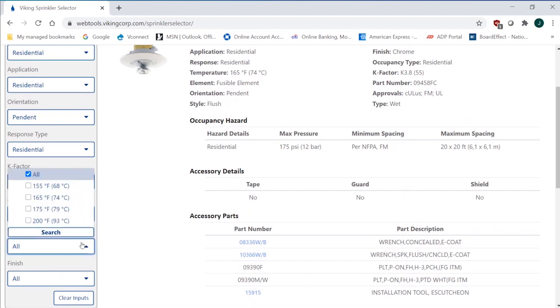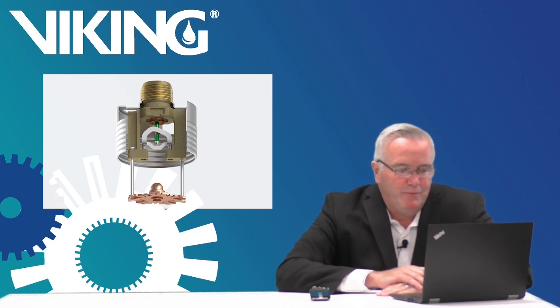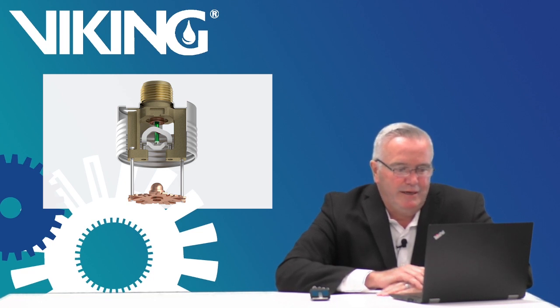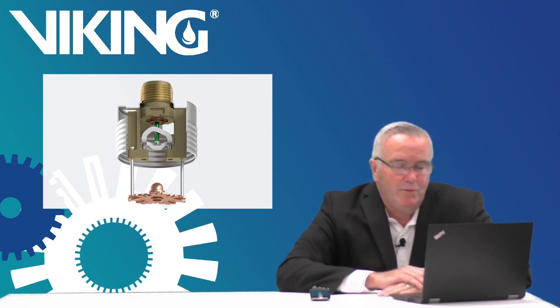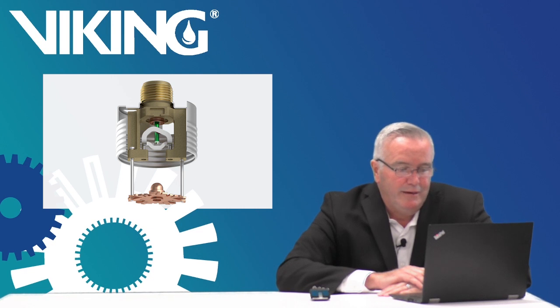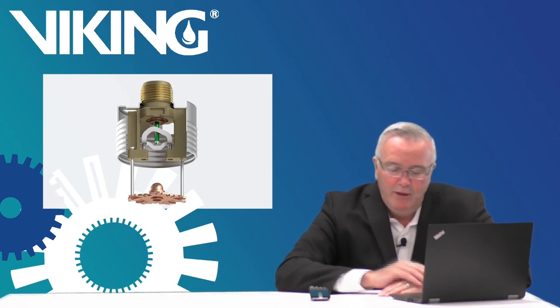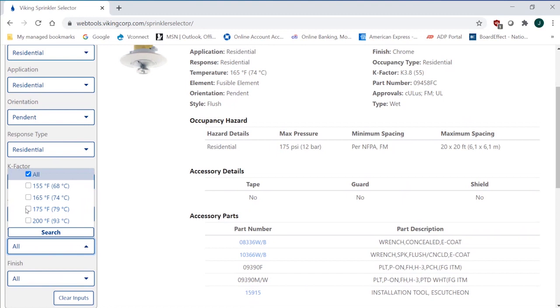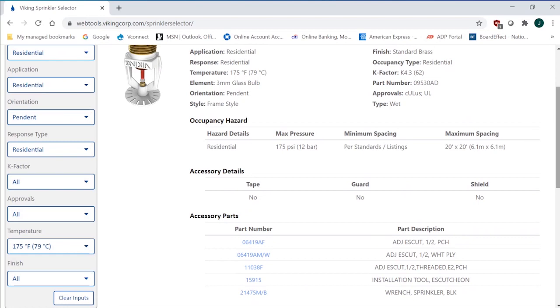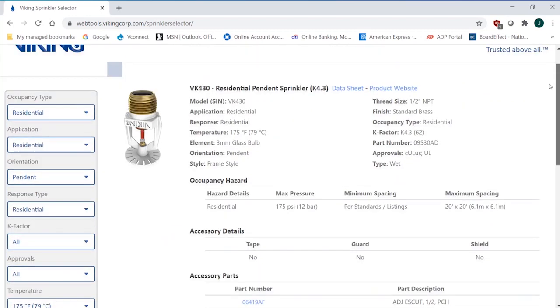Let's talk about temperature. I'm going to use this opportunity in the platform to tell you, please use intermediate temperature. I know we have the 155. It's required in a lot of places, and it's a good sprinkler. But I've seen a lot of applications where people leave homes unconditioned for time or their residential application unconditioned for certain times. And we've seen some activations of some sprinklers due to temperature. So the 175 can be used if you expect your ambient temperature to go above 100 degrees. So 175 is the same. We have many applications of the 175. We pride ourselves in that. So if I pick 175 and hit search on the pendant, you can see that I went to 53 entries.